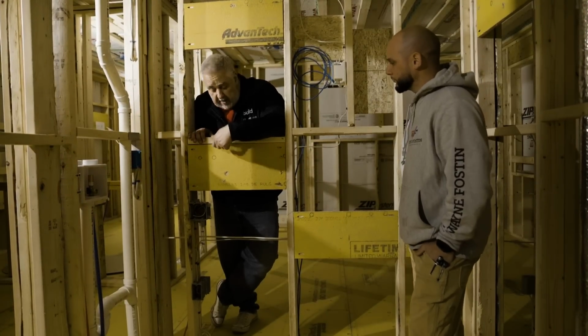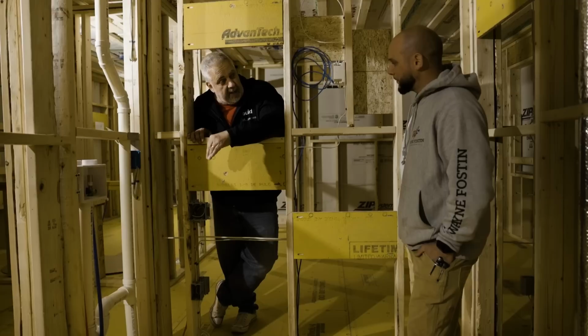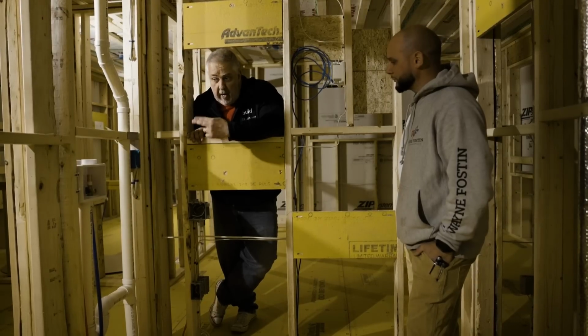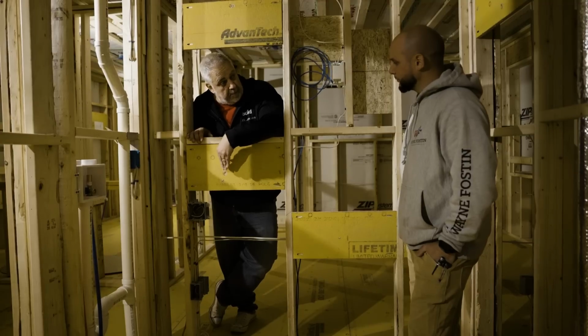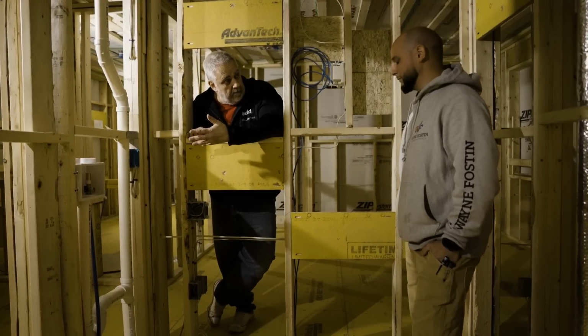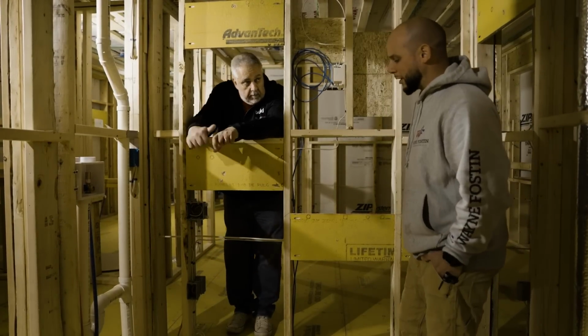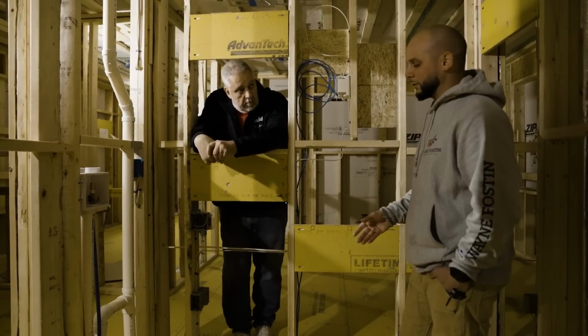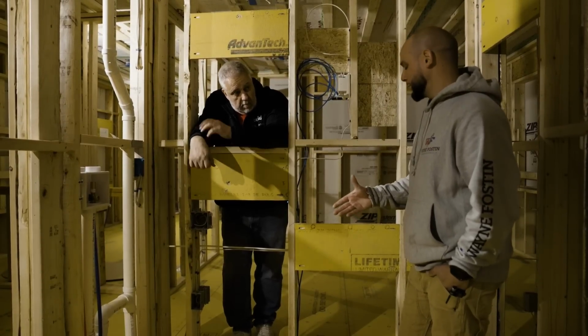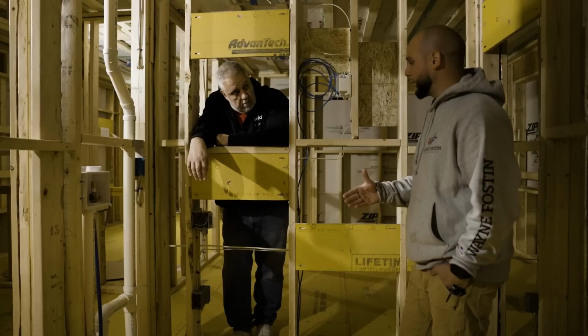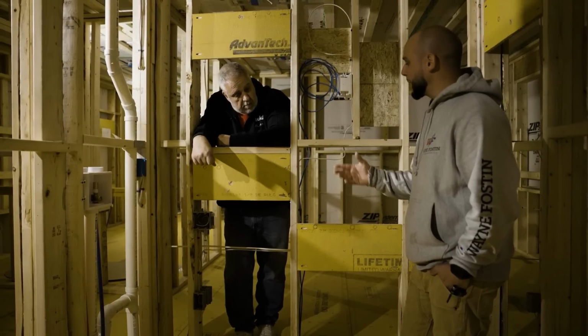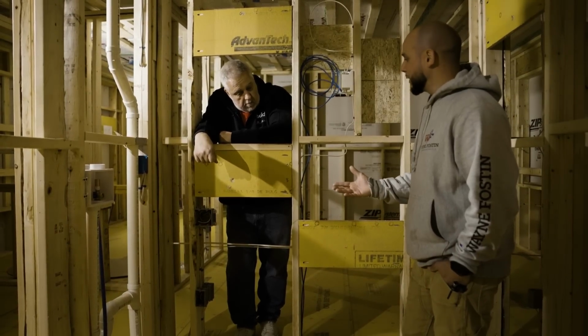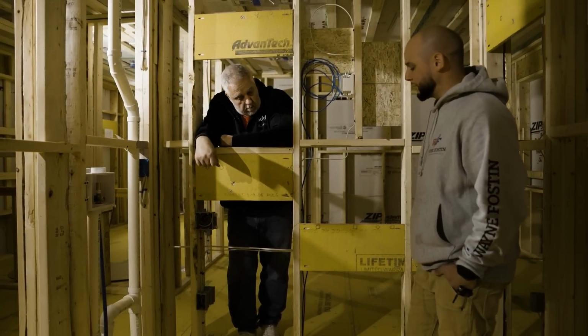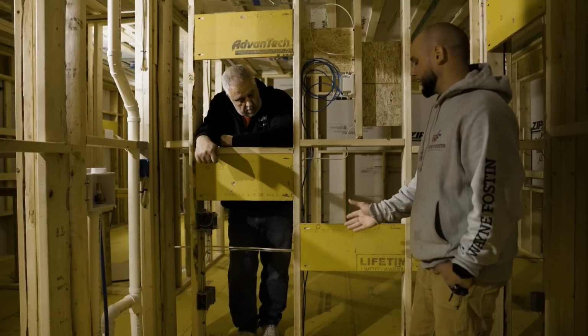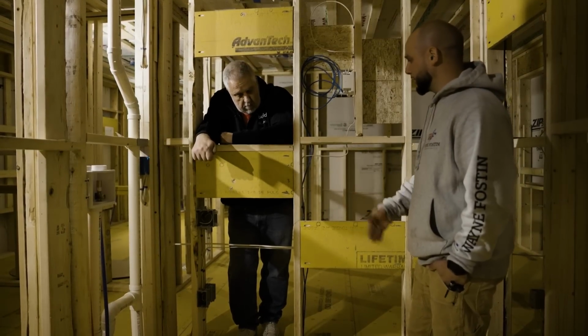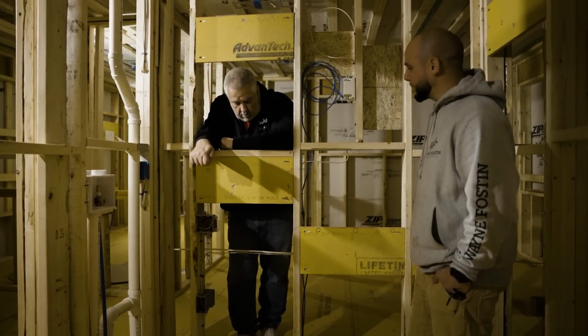And get pumped out. Because I was going to ask, where does that go? Because you can't really hook that drain to the regular plumbing, because if it has a trap, it's going to dry out. If you hook up to the regular plumbing, it gets a little bit more complex. You need to trap it out, and you'd also need a trap primer. Because it's going to be a drain that hardly ever sees water, that trap seal would eventually dry out, so you would need to install a trap primer on that. So the best bet is to get it out of the sanitary system, and in this case, we put it in the sump pump pit.